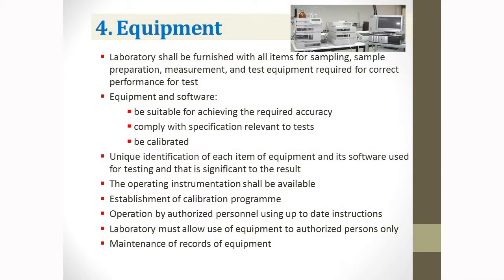The next point is equipment. Your laboratory shall be furnished with all items of equipment or instruments needed to carry out your test methods — this relates to sampling, sample preparation, and measurement. Software also belongs to equipment. Nowadays instruments have more and more software, and this should always be included. Equipment and software must be suitable for achieving the required accuracy.